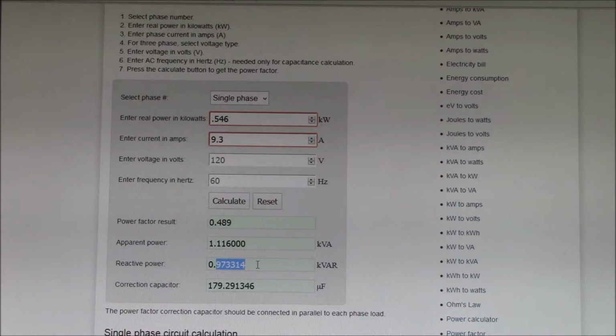But if you are running that same device off of a power inverter, you essentially are paying for kVA because your inverter needs to generate all of this apparent power. In this case, I've got a power inverter and I've got a washing machine plugged into it. The only way to make that washing machine motor run is to provide 1.116 kVA of apparent power to get it to go. Or I could come in and add this correction capacitor, which would provide this reactive power to operate the motor. If you're running inductive loads off of a power inverter, you may want to consider power factor because it does matter. Now this applies to my particular inverter, which uses a transformer to produce the output voltage.